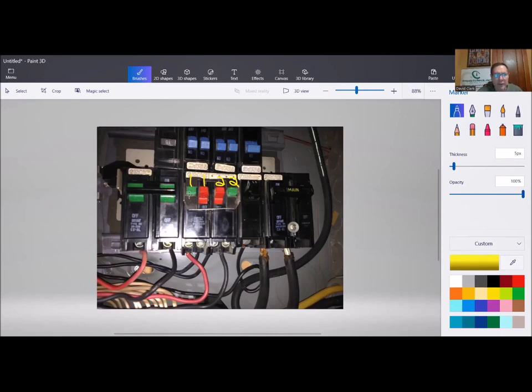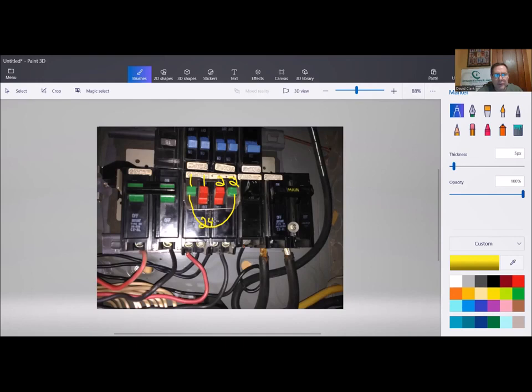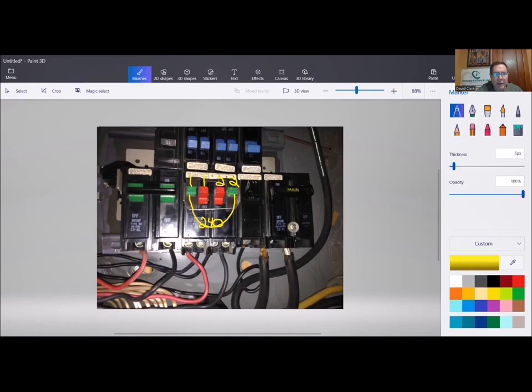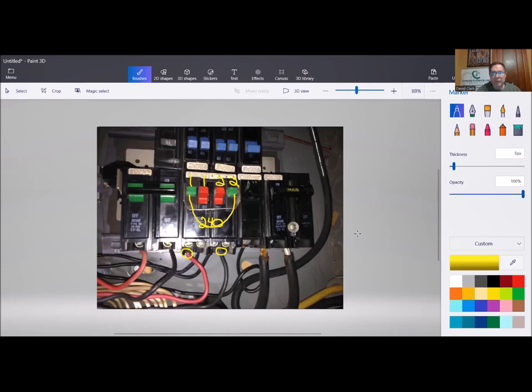So these could be together, but these have to join. So let's take a look at this one. This is the first 240 volt we'll look at. And we're just going to write 240 there because we know that that's what that is. It should not be a multi-wire branch circuit because they're supposed to be internally and externally linked. And this is an older breaker. I'm guessing that it's not internally linked or we call that a common trip. This particular breaker would more than likely be an independent trip. So we look at the 240 volts here and we're going to come down, follow this green because that's one leg, 120 volt leg, and there it is. Then we follow this green and that's going to be another 120 volt leg, thus creating our 240 volts. Again, shouldn't be a multi-wire branch circuit.